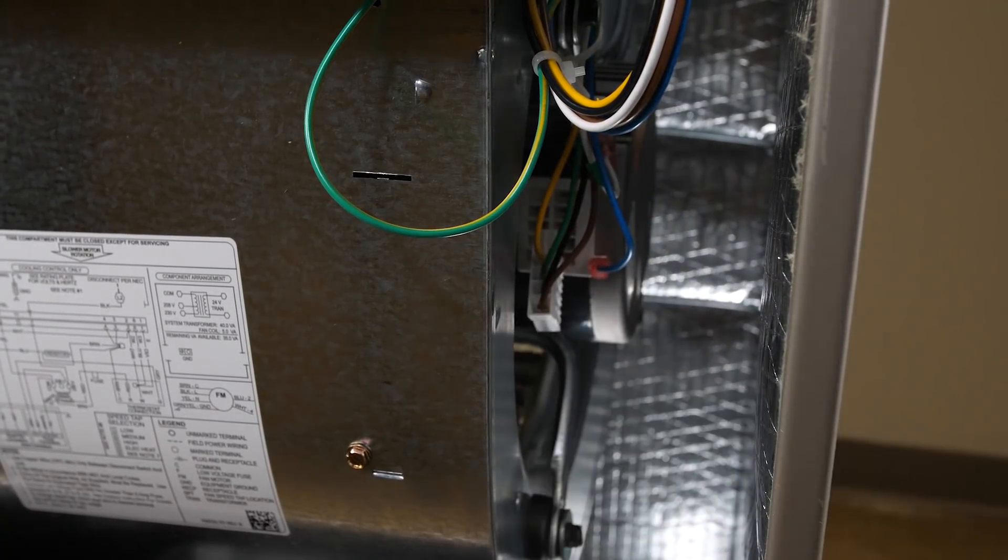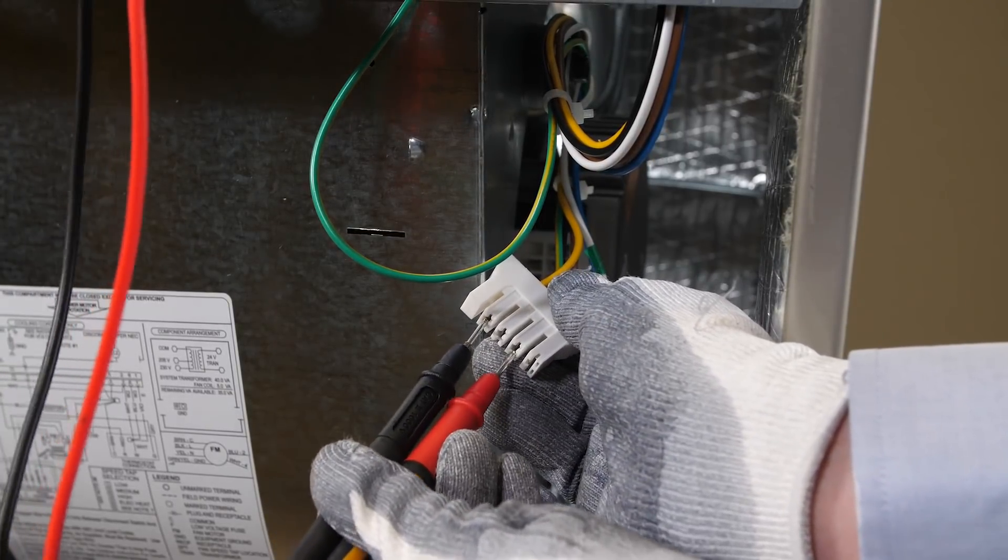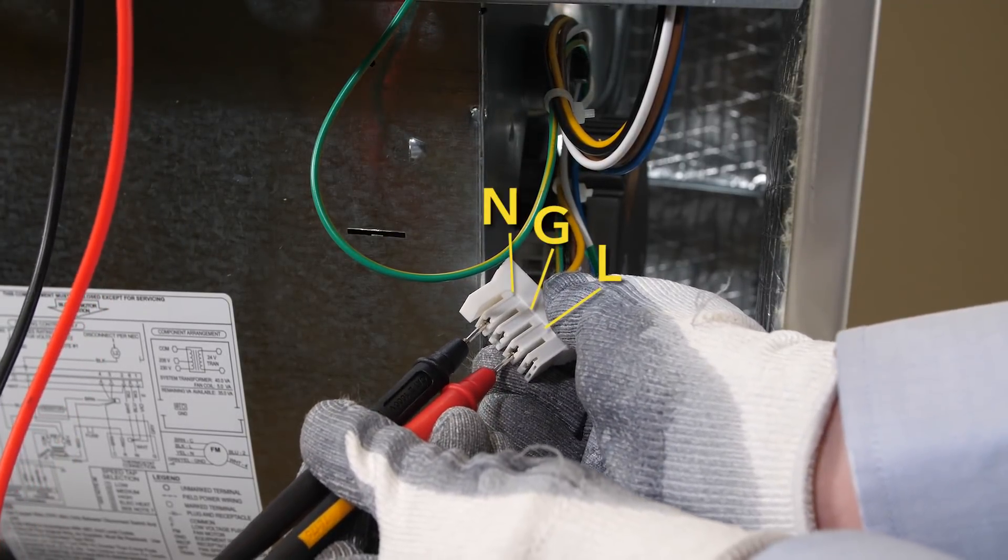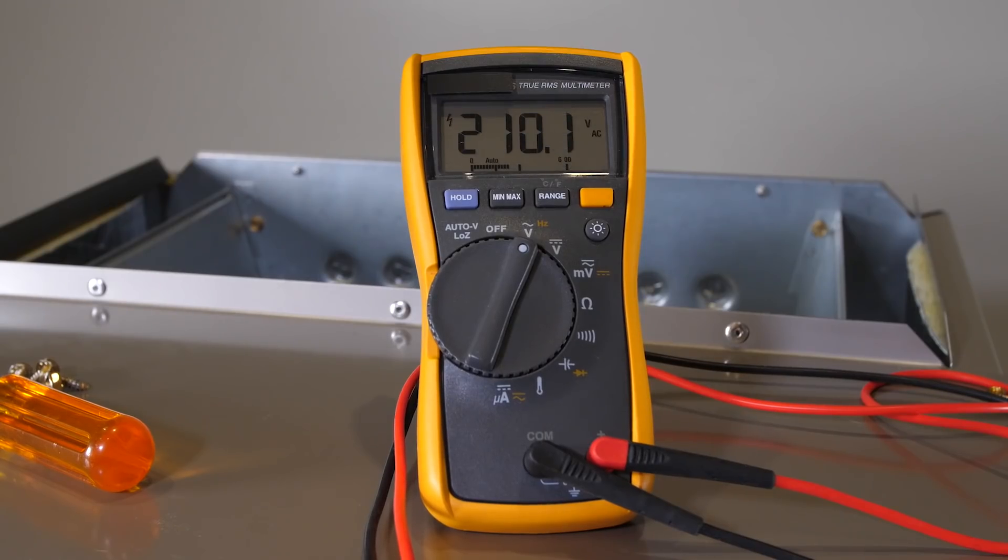Turn power back onto the unit. Using a voltmeter, check for proper high voltage at the L, G and N connections at the harness. Voltage should read between 208 and 230.